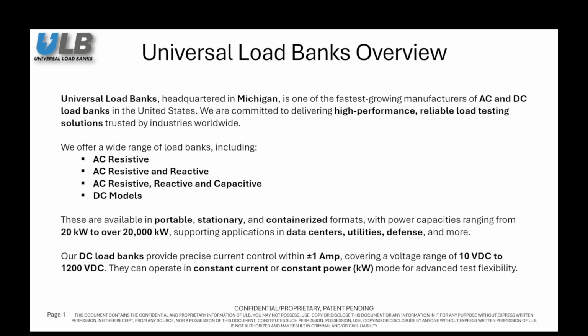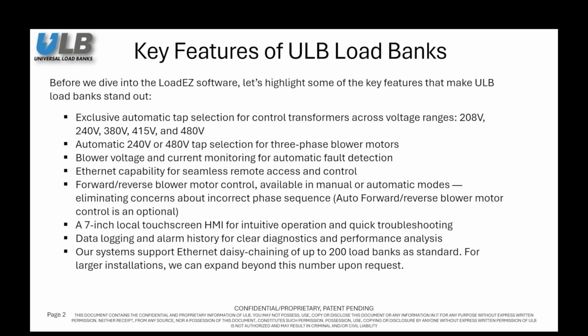Our DC load banks provide precise current control within plus or minus 1 ampere, covering a voltage range of 10 volts DC to 1200 volts DC. They can operate in constant current or constant kilowatt mode for advanced test flexibility. Before we dive into the LoadEZ software, let's take a moment to highlight some of the key features that make ULB load banks stand out.